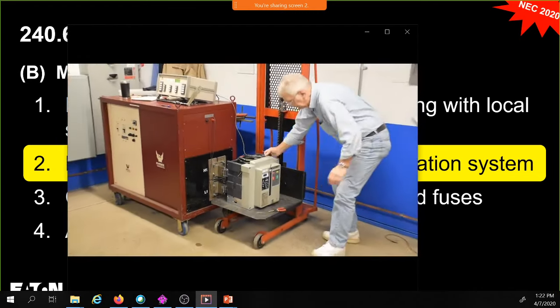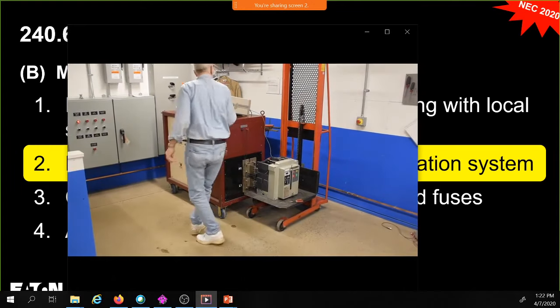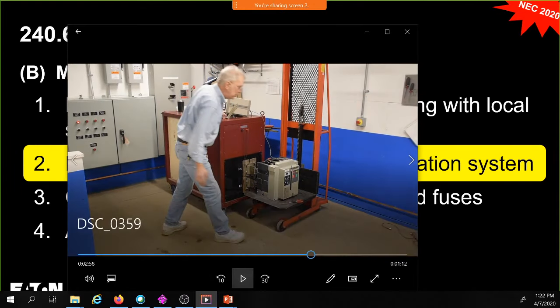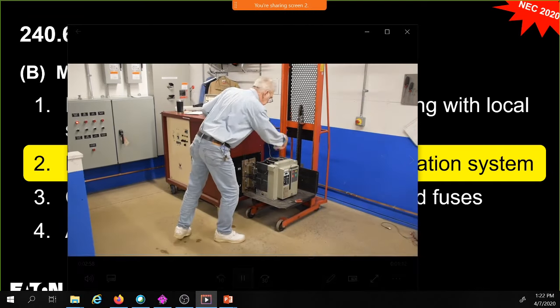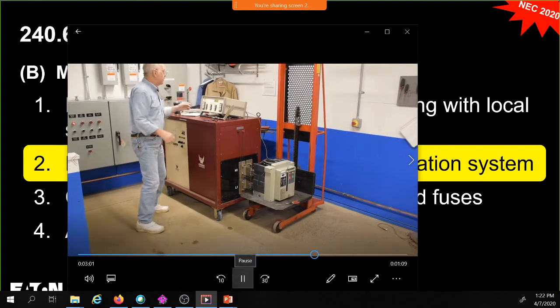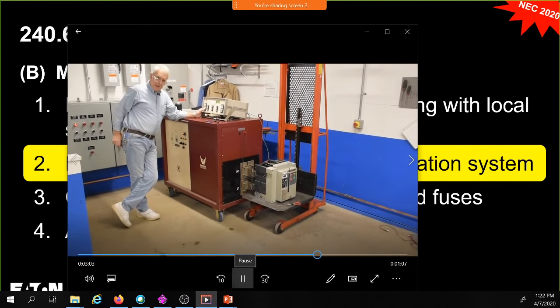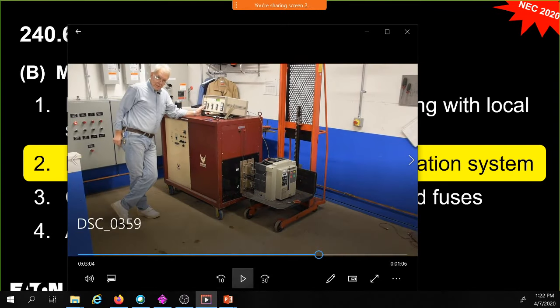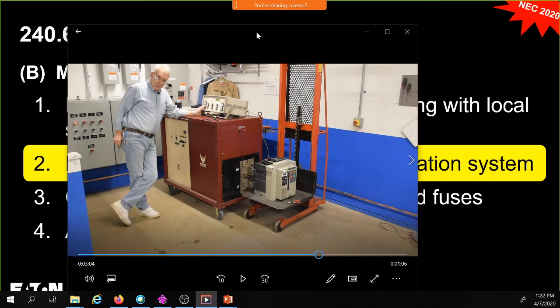The piece of equipment you're looking at right here is the Phoenix, which is a heavy device. It's pretty sophisticated. It can put out a lot of current. Okay, breaker's closed. So what we're going to do, 2.5 times. I'm not going to waste our time watching too much of that, but he'll inject current through here. This will open and trip. It'll tell you the current value that it tripped at, and then he verifies that it's functioning.